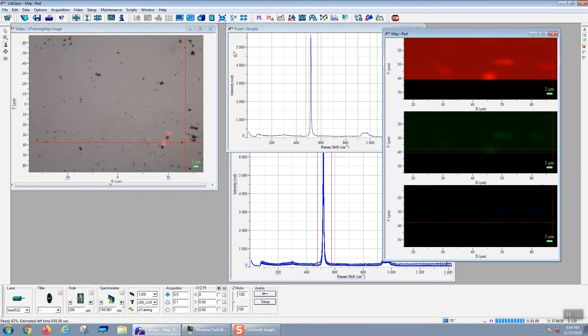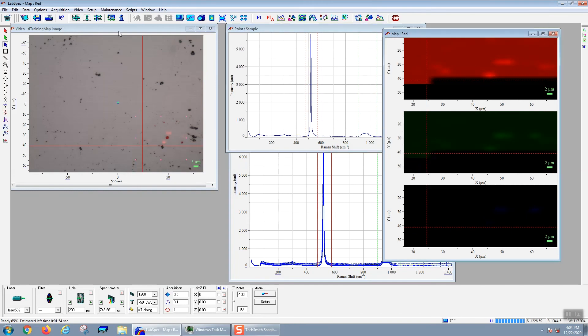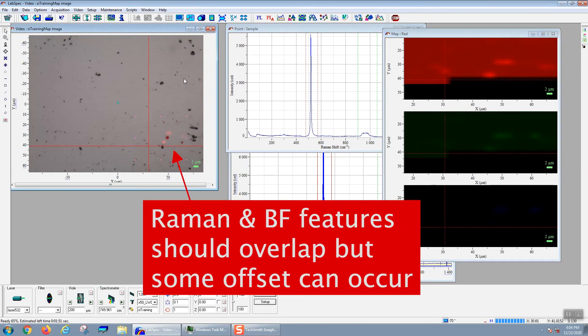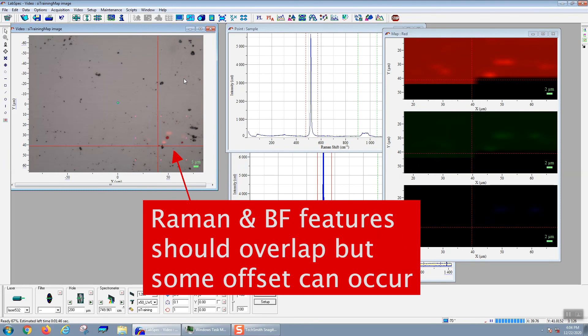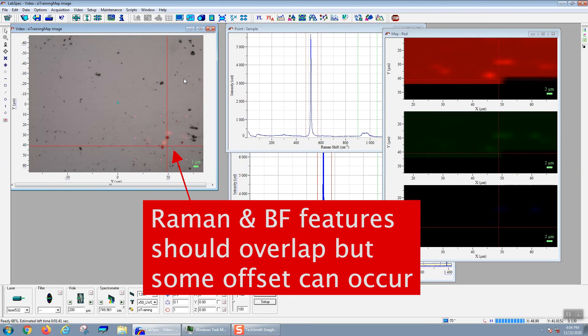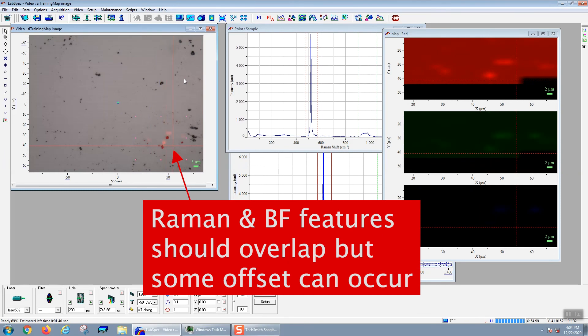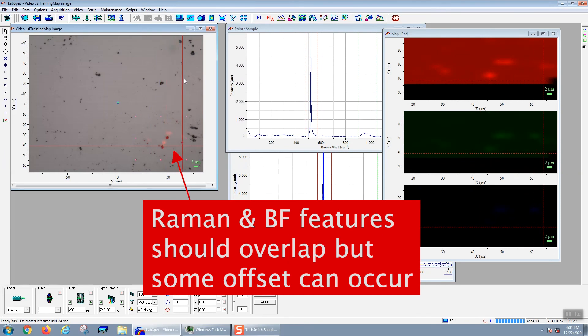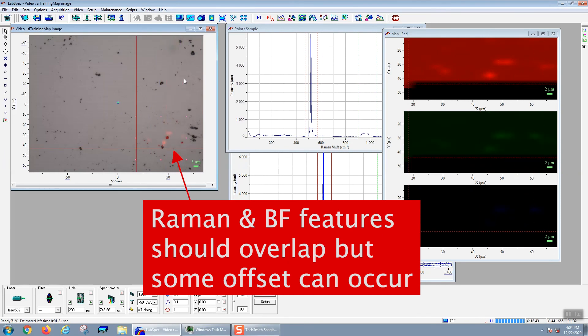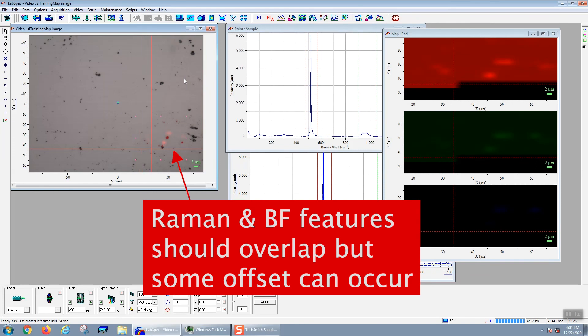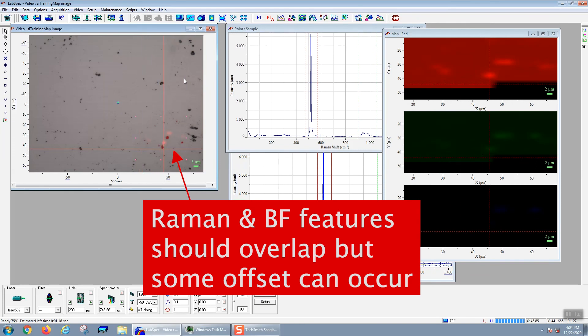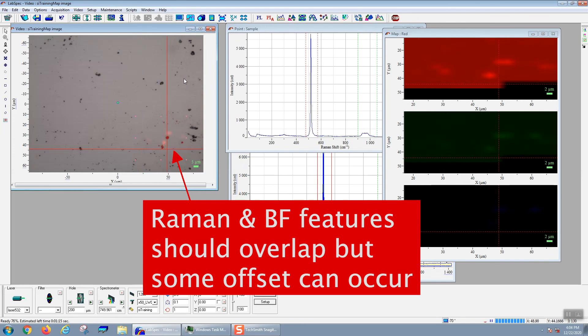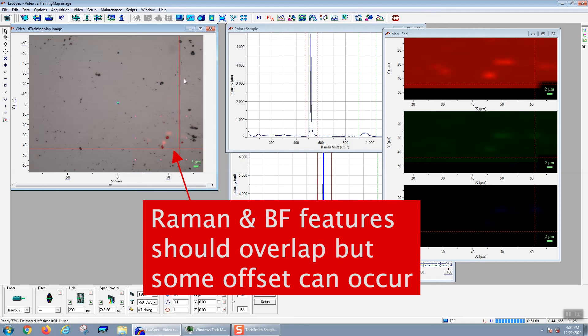You'll notice that the points generally correlate to the map, but they can be shifted in the X or Y directions. This can happen either because the calibration of the stage is not correct. Otherwise, the detector sometimes can be adjusted in terms of their parameters to correct this kind of offset.